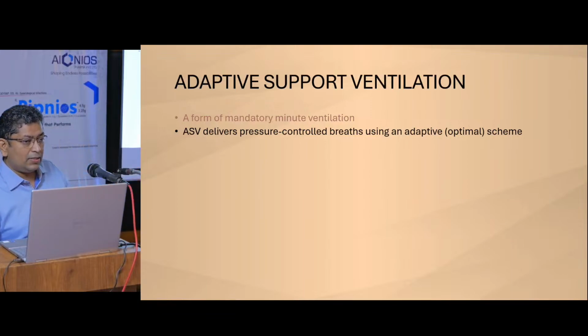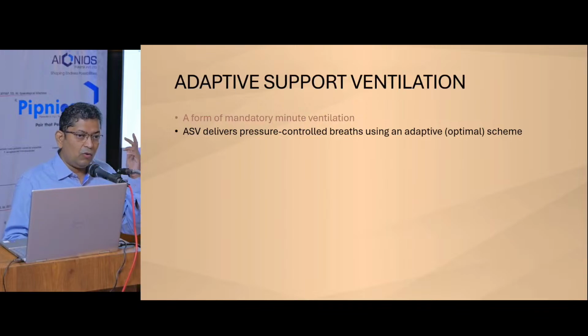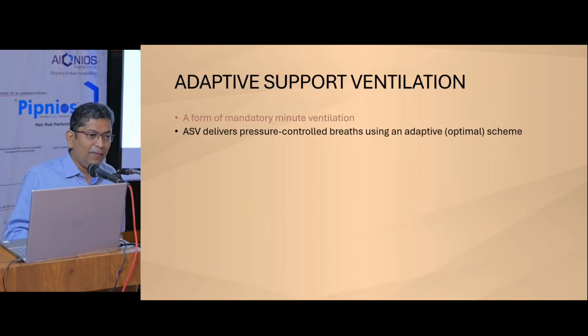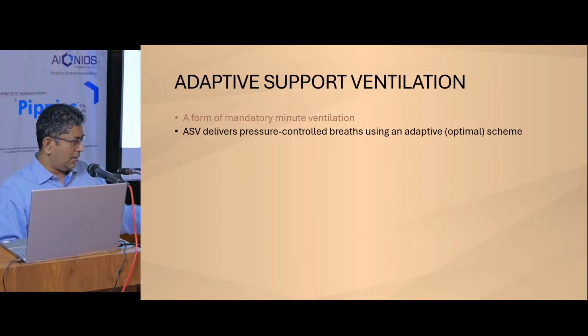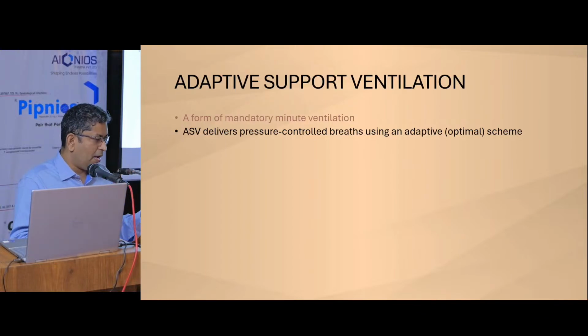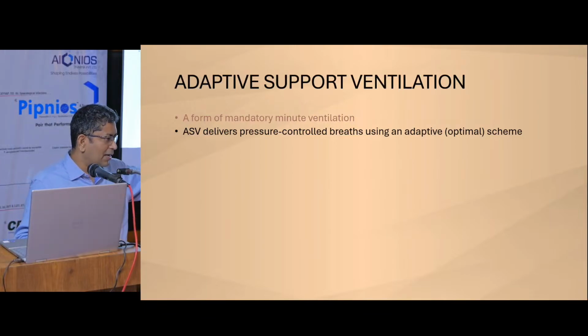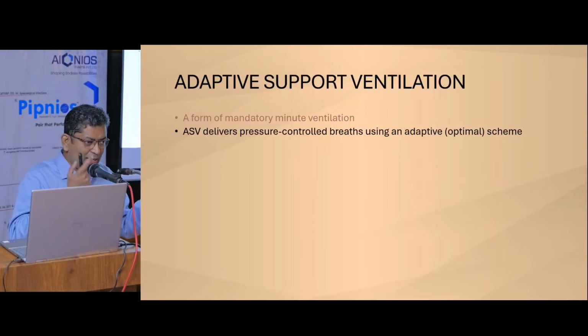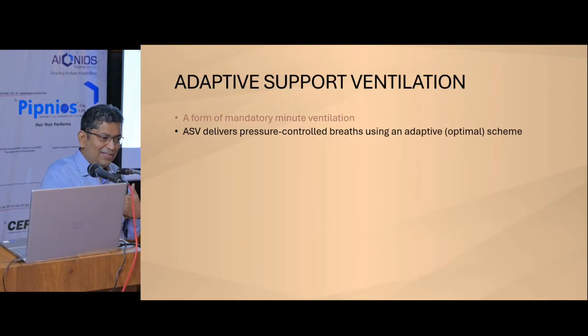So how it does this is it uses something called the Otis formula. The Otis formula is from 1950, before your parents were around, most of you at least. It's an old formula which looks at the compliance and the resistance of the respiratory system and finds out the best respiratory rate and the best tidal volume to give the minimum amount of energy to the lung. That is what it is calculating. The idea is we normally breathe at that minimal level of energy that we need.